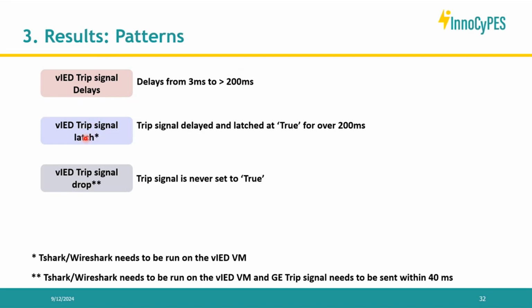And the second is what we call a latch of the signal. This was a quite weird behavior, but very simply explained. Once the trip signal from GOOSE is sent to clear the fault, usually there's a reclosure mechanism that says after a few seconds the trip signal should pass back to false, so that the fault is cleared. The circuit breaker won't stay open forever if it's not a permanent fault. So another behavior that we observed while running the resource exhaustion attack is a latching of the trip at true.